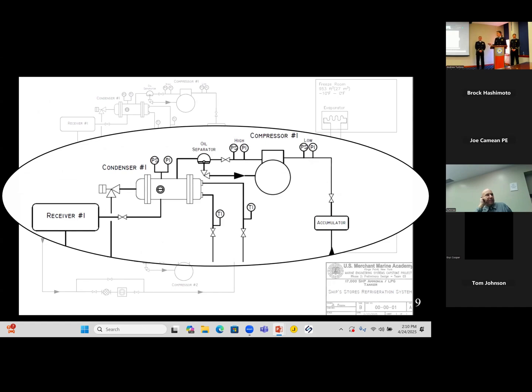There are compressor high and low pressure safety switches to automatically operate the compressor based on the pressures. For the high pressure cutout for the compressor, there's a 400 psi cutout and a cut-in, which requires to be manually reset. And for the low pressure cutout for the compressor, it's a -3 psi cutout with a cut-in at 50 psi. From there, the superheated vapor refrigerant will travel through the oil separator, a water-cooled condenser equipped with a pressure relief valve set at 430 psi, which is compliant with 46 CFR Part 58. And then lastly, the receiver for repair and manual takedown of the refrigerants in the system.